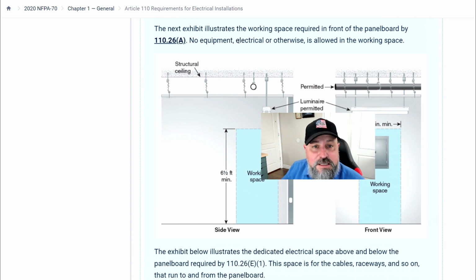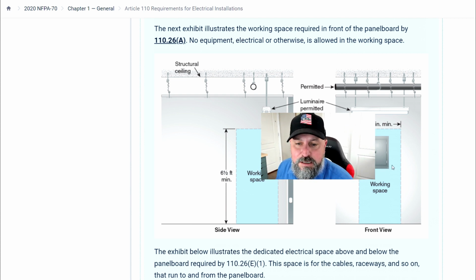The next exhibit illustrates the working space required in front of a panel board by 110.26A. No equipment, electrical, or otherwise is allowed in that working space. So this is showing a side view and a front view, right? So luminaires are permitted. The sprinkler fire pipe is permitted above the working space. You see that it's not directly above the panel, it's in the working space. And you have to have 30 inches from any other equipment on this right here, except if it's another panel, they can overlap.